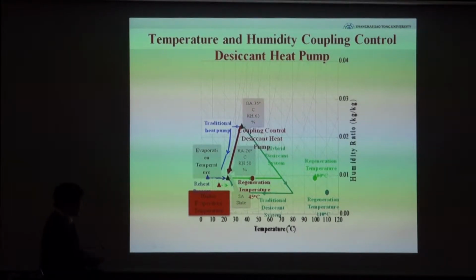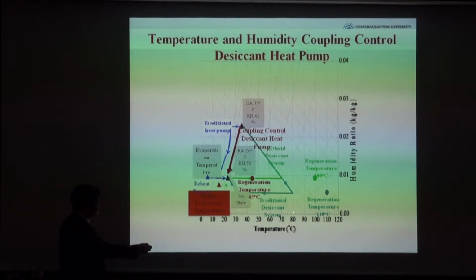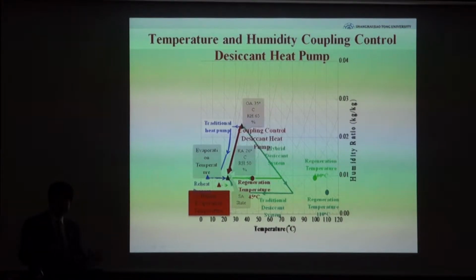Now, there are several ways to use desiccant materials to dehumidify the air, maybe one stage or maybe two stages. For very dry air, the temperature will be increased due to adsorption. So you combine them together, get the cooling down, and then apply evaporative cooling. This is the normal approach for solid desiccant cooling. No other equipment is needed, but you need deep dehumidification. In this case, you need a desiccant rotor or liquid desiccant. You need solar heating for the regeneration, and the solar heating temperature should be higher than the regeneration temperature. So if it's 80 degrees, then you need solar heating at 120 degrees centigrade. In this case, it's not so reasonable.